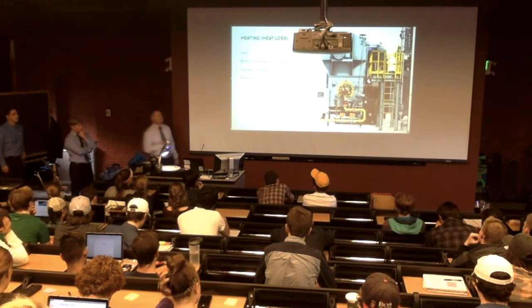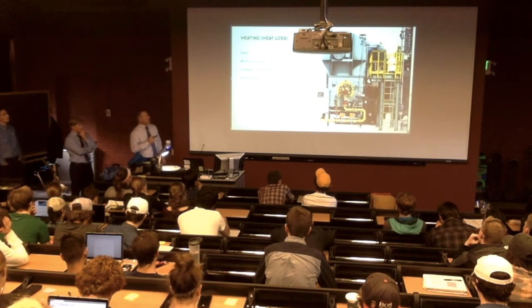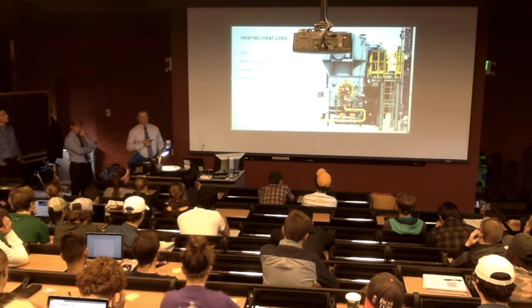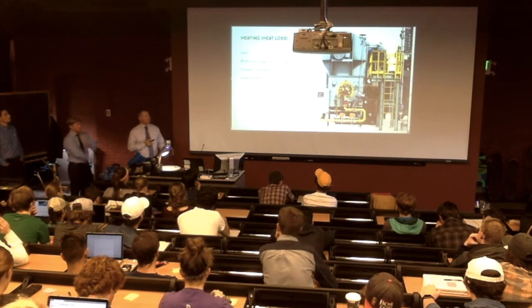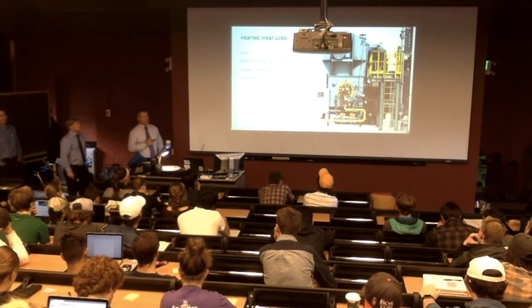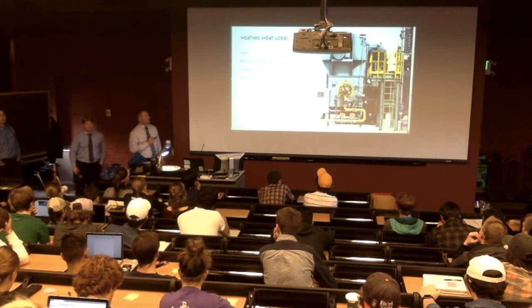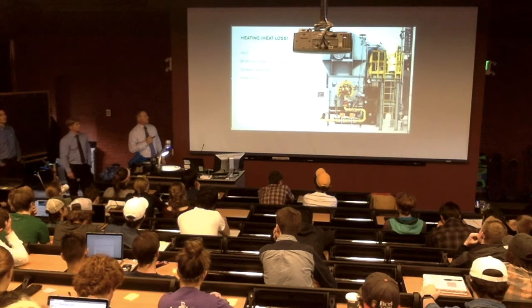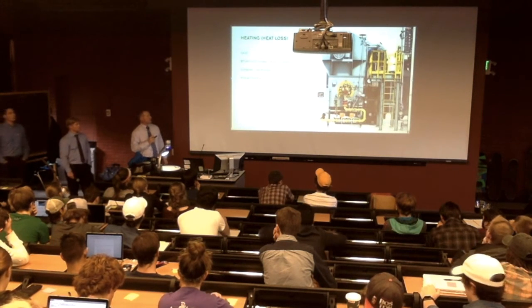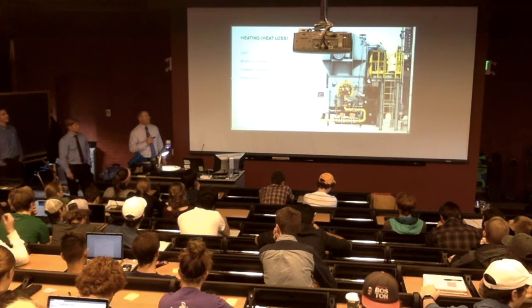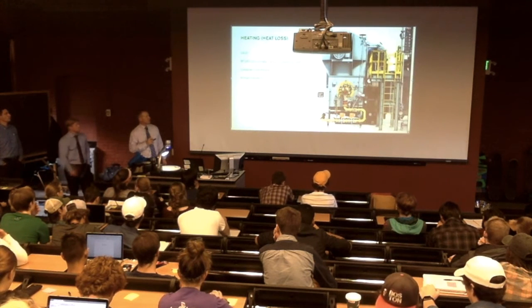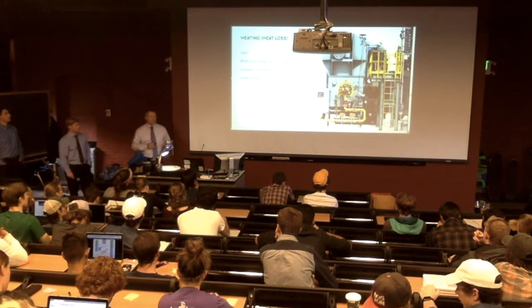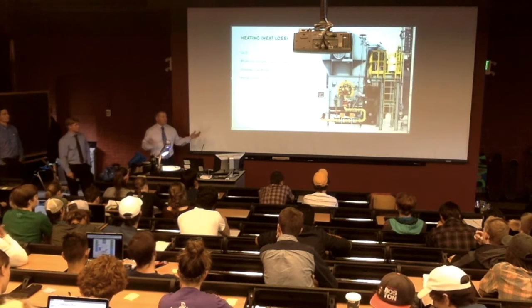So we figure out, and I'm not sure if you're taking it in SI units or BTUs, but in the United States, everybody uses BTUs as opposed to kilowatts. So we use BTUs per hour as the flow rate through the wall. It's the U value times the area times the temperature differential. We used to do this all by hand, but now it's all computerized.